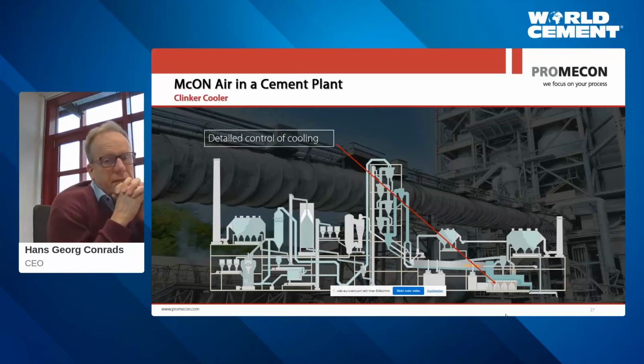Last but not least, another thing that we have been asked for several times is the balance of the clinker cooler. You have at least 5 or 6 fans that blow cold air into the clinker cooler. And then you have several branch-offs that come out of the clinker cooler. You have the waste heat recovery, you have the tertiary air that's branching off. So you have several airflows that go out of the clinker cooler. Now, one big flow, of course, goes undetected, and that is the main gas flow, which is the secondary air into the rotary kiln.